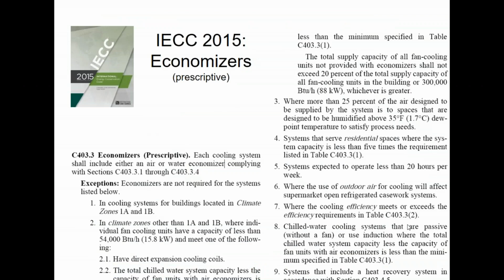So what happens with the economizer? When do I have to do the economizer? So per IECC, an economizer is required when you have 54,000 BTUs or greater of cooling capacity. Basically 4.5 tons, you'd have to have an economizer. As you can see, there's a whole page of exceptions to that. Most of those exceptions do not apply to most of your projects. Some of them may, right?